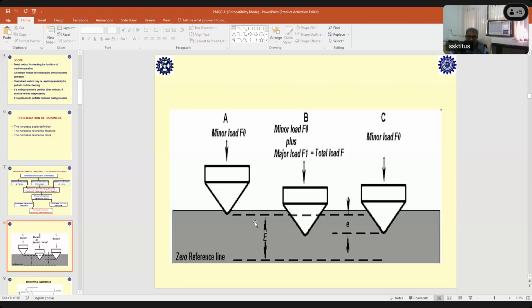What we are doing here is simply applying a 10 kg initial force, then applying some additional test force as per the requirement of the scale, whether it is A scale or B scale or C scale. All these three scales have different forces. Then you remove that additional test force and measure the permanent indentation depth. So now the dimensional component is coming in, because we are measuring the depth.